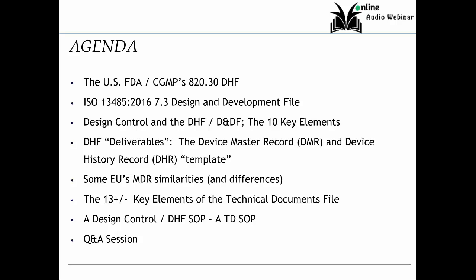We're going to look at what they lead to in terms of your further documentation, like your device master record and your device history record, or your master production record and/or lot record, depending on where you're located in the world and what terms you use. We're going to look at some of the similarities between the FDA's requirements and the medical device regulation requirements in Europe, or the old medical device directive requirements. And we're going to talk about the technical file, the similarity between a technical documentation file and a submission to the FDA for device marketing clearance or approval, 510(k) or PMA. And we'll look at some possible templates for SOPs on design control and technical documentation, especially focusing on the quote-unquote essential requirements / general safety and performance requirements of the medical device regulation in the technical documentation SOP.